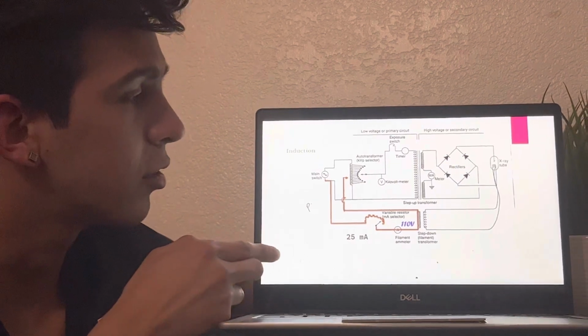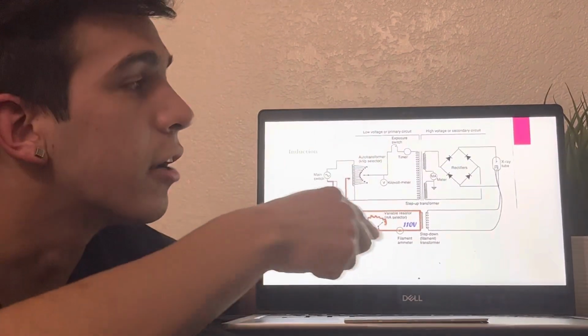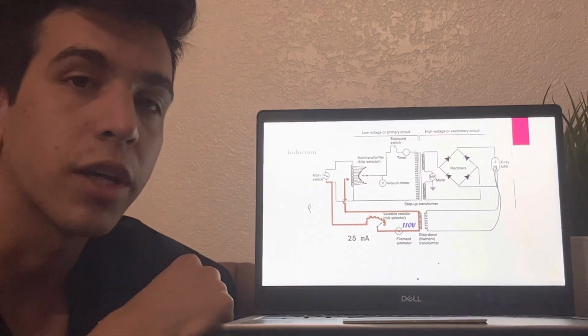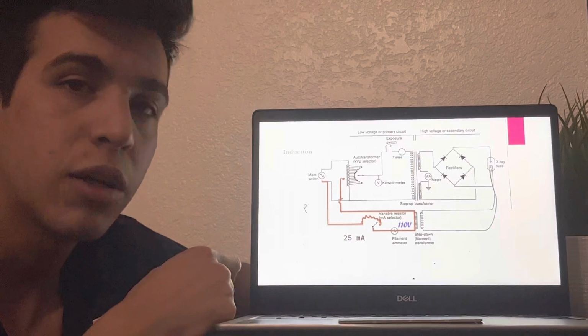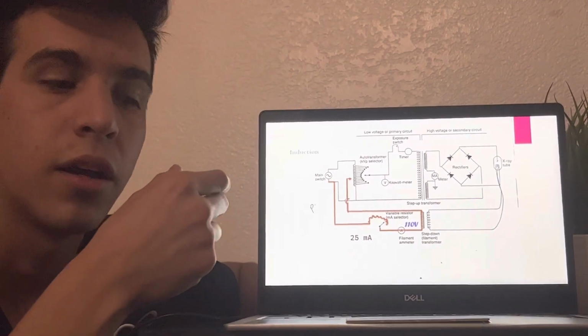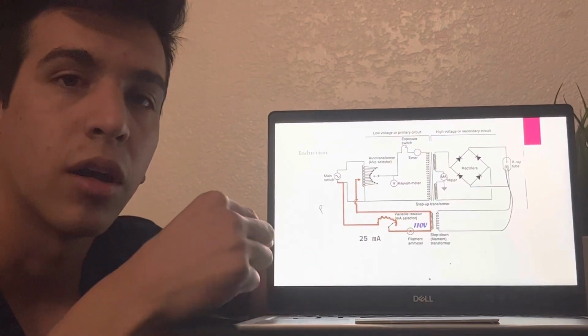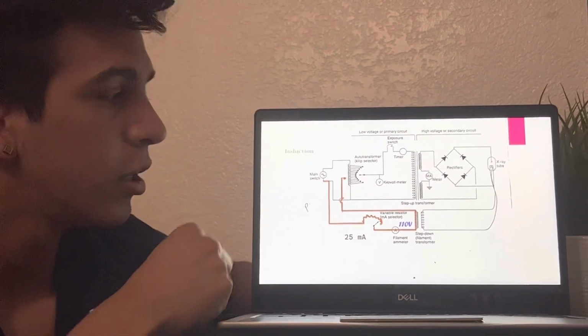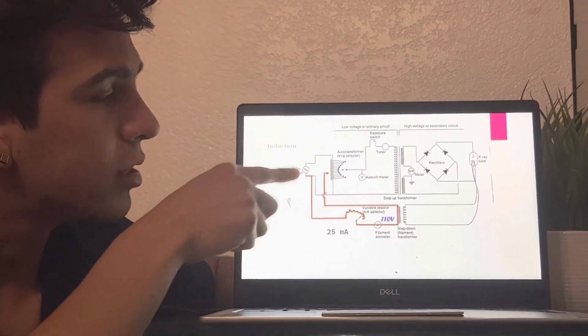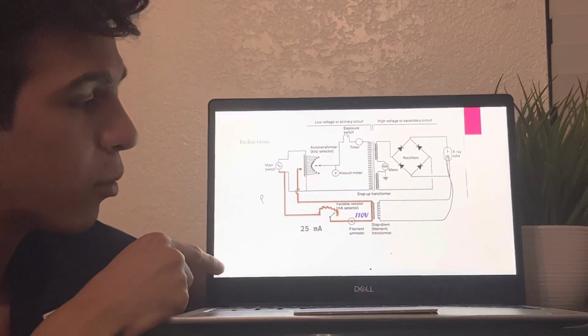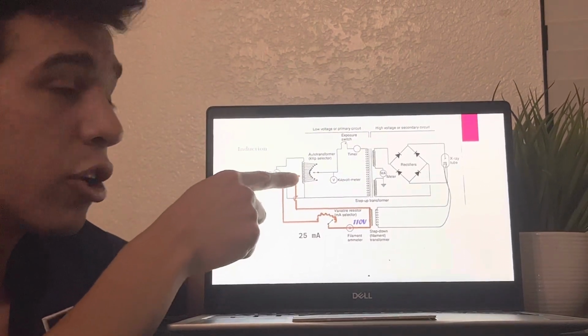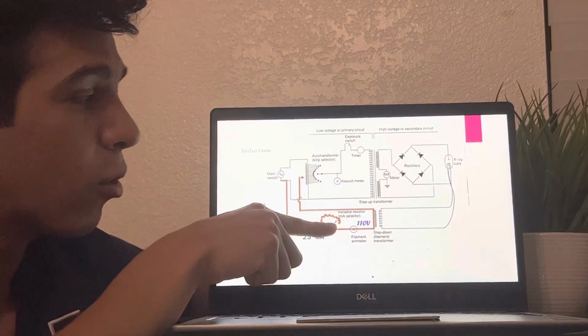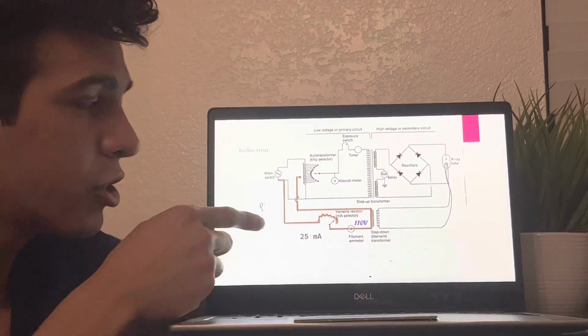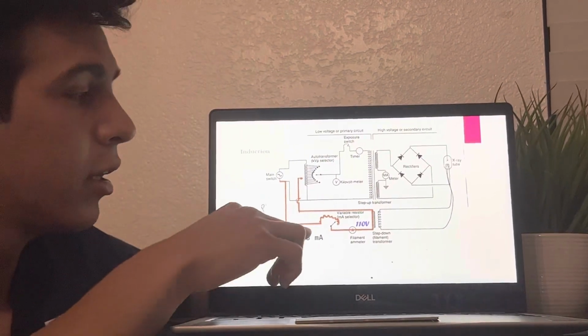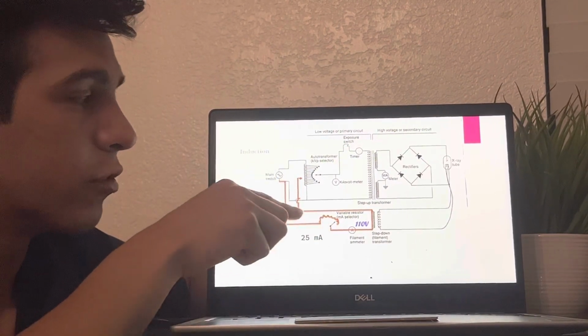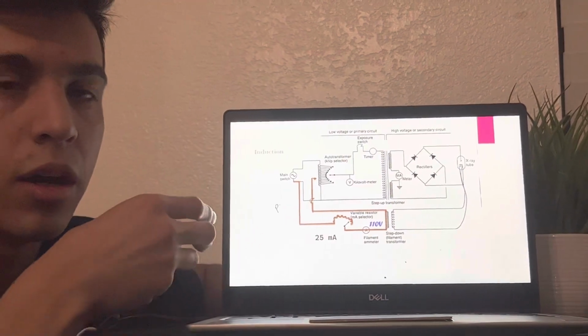And the way that it does this is through induction. There are going to be several places inside of the X-ray tube and X-ray circuit that have induction. And basically, induction is electricity jumping a gap by the use of magnetic fields. So right here and over here, the wiring is not connected. The reason for that is that if they were connected, it could confuse the machine with the kVp or mA selector. So the induction makes it so that everything can flow properly and fluidly through each of them without touching. And so it jumps the gap, which is induction.